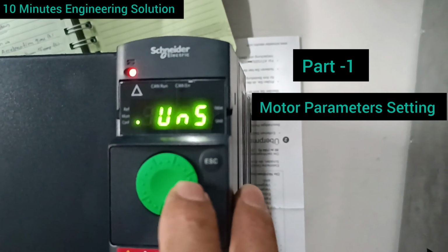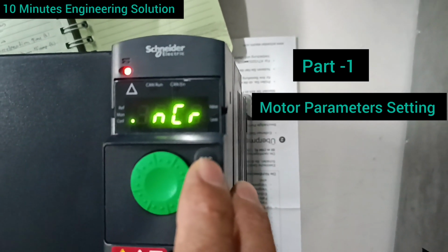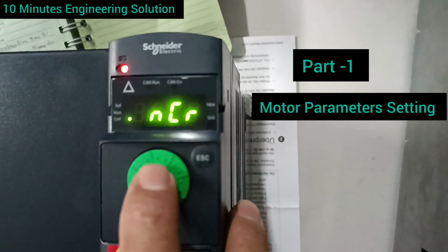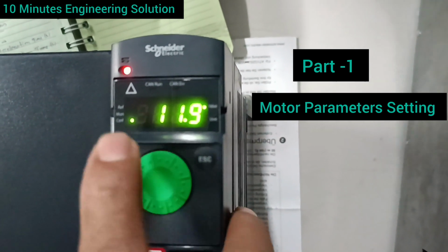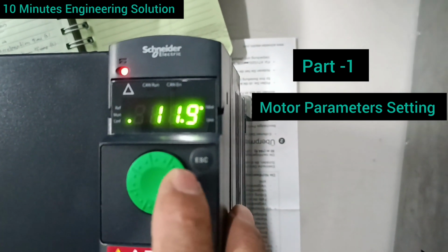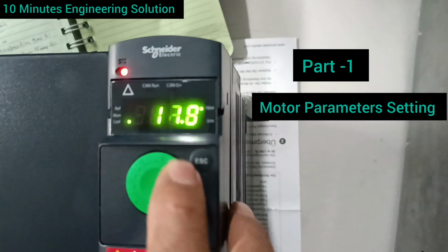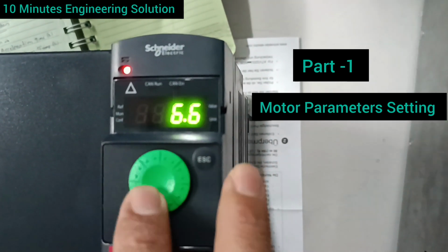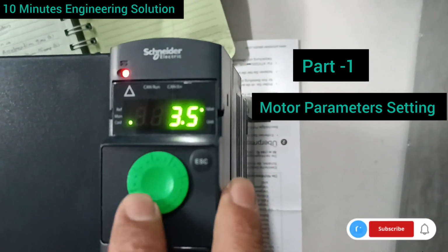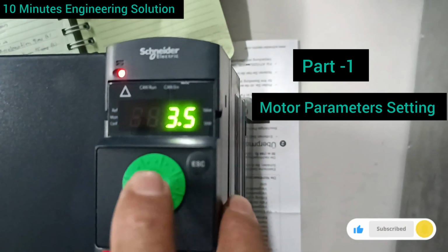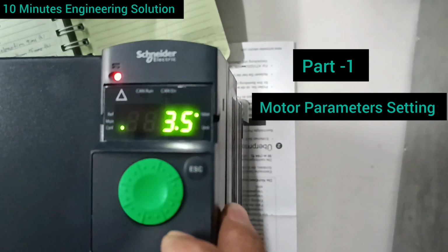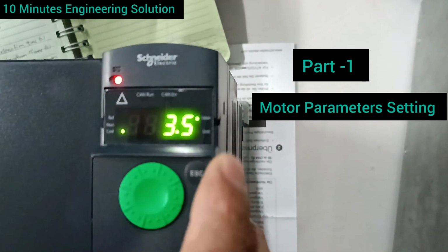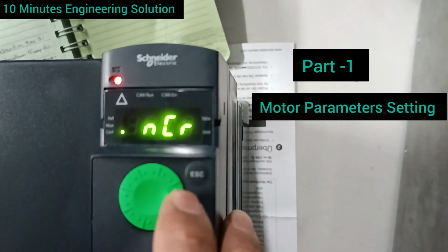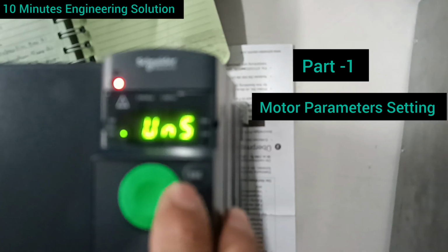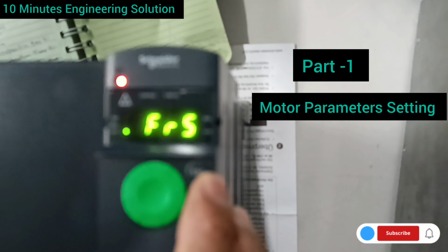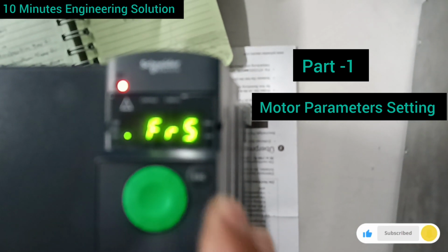And then NCR, you can see the next. NCR, rated motor current. You can see the picture here. As per design, the 5.5 kilowatt VFD has a current of 11.9. My motor sizing is 1.1 kilowatt, so I'm setting a lower current, 3.5. This is the 1.1 kilowatt setting as per design. This is NSP. You can see the next setting.